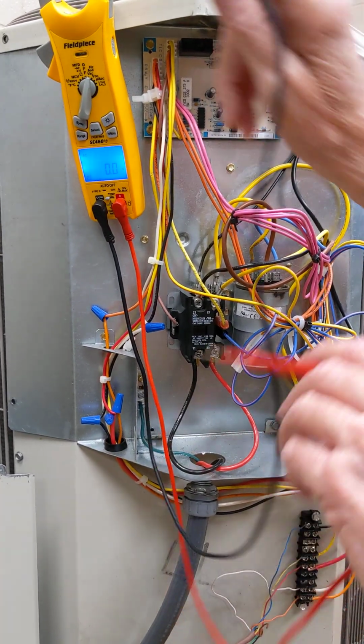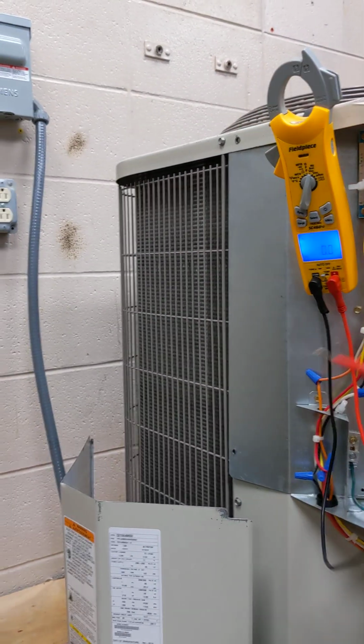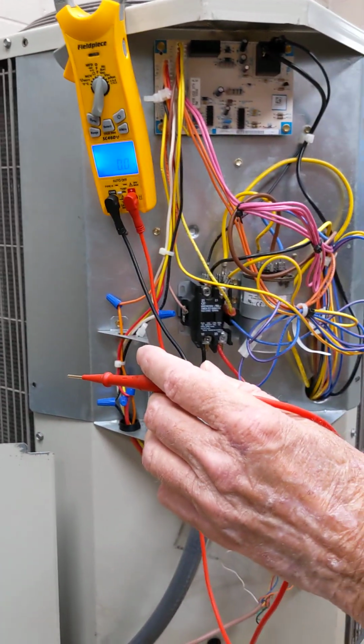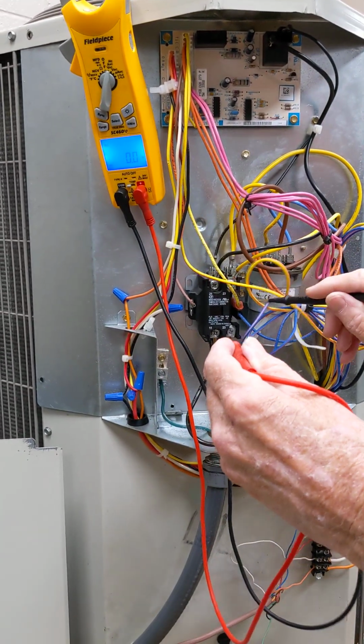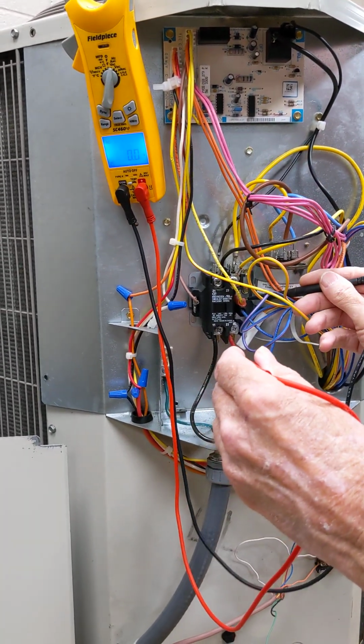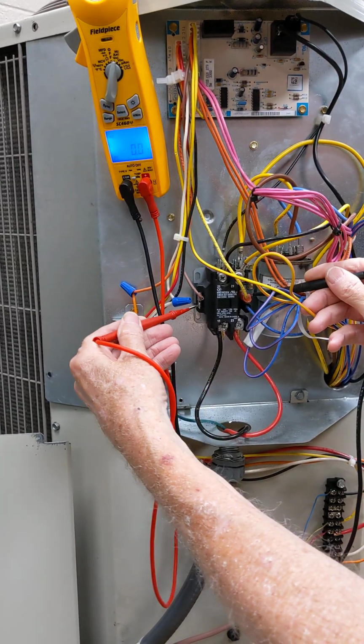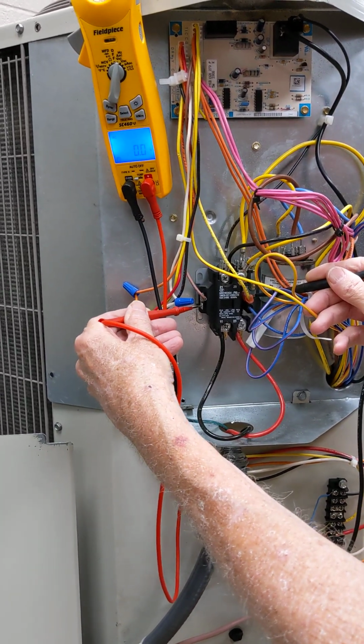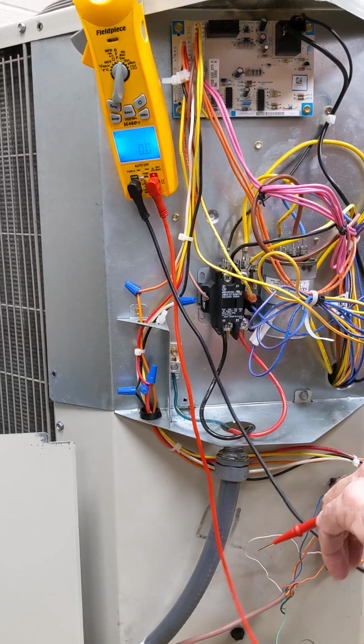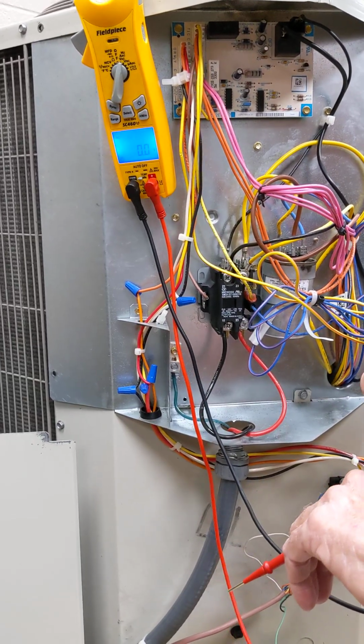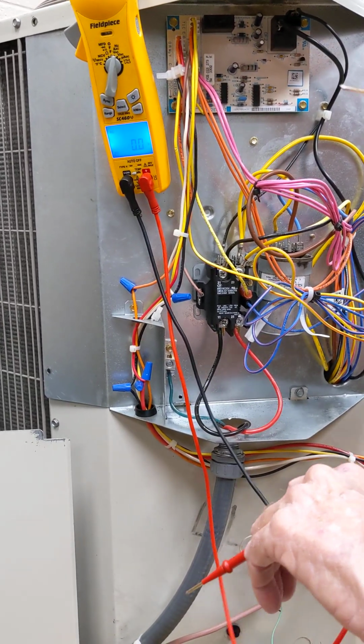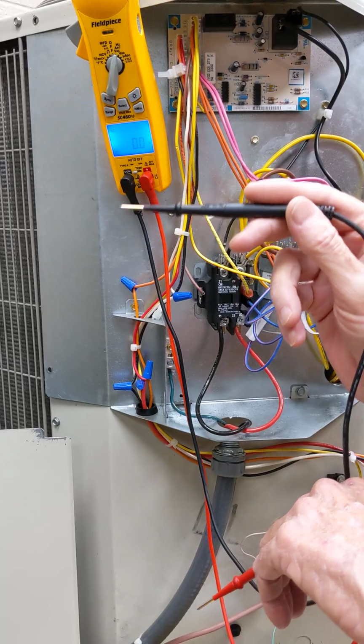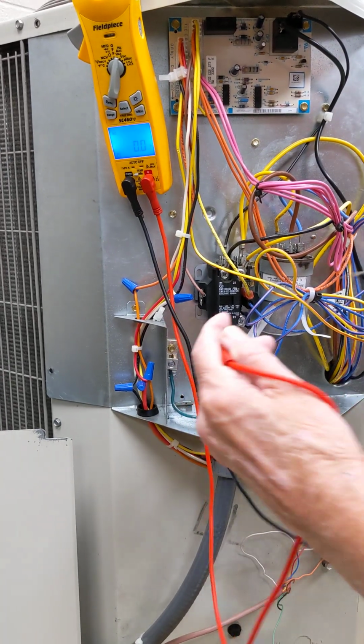I've left the high voltage going to the motors on, but I turned off the cooling call. So, yes, I still have voltage here, I guess. No, I don't, and I don't have voltage. Why is that? Because I do not have a call from the thermostat. So it is not taking the R inside the thermostat and connecting it to Y to bring it out here.